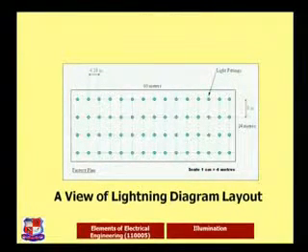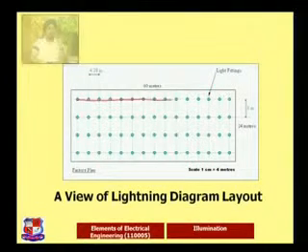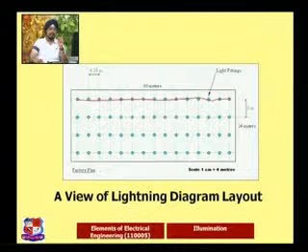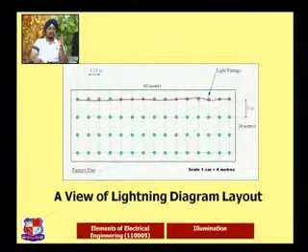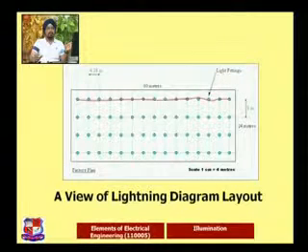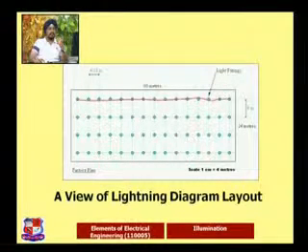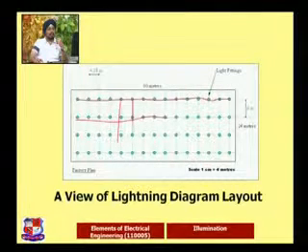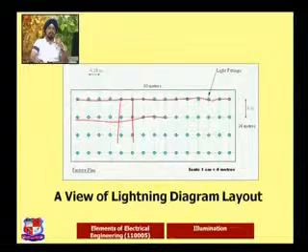What we last discussed, how to place the lamps or the fittings in the area. See, random placement is not possible. So for one ideal diagram for a particular area, we selected the number of lamps or fittings with a proper spacing of 4.28 meters. The room is there for the whole 60 meters, and the light fittings are divided into rows and columns according to our calculation.